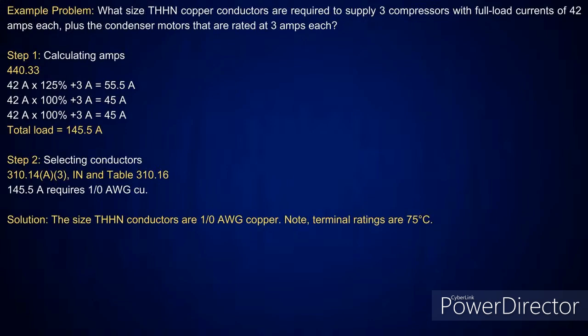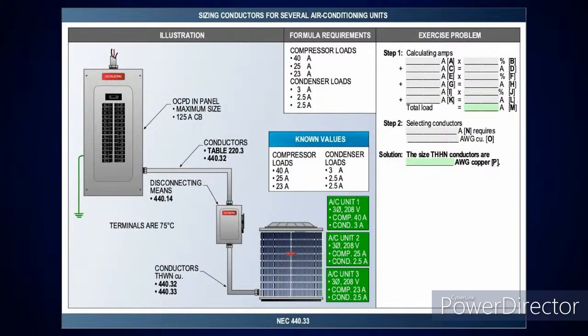Now, the thing I like to point out here, have I changed any of these calculations really? The format, the layout, everything is exactly the same. The only thing you've got to remember is how to do each one of them. You just have to be careful, because you don't want to assume you can just wire everything with a 1-aught. This was just to show how all this worked. We did it in a single line diagram because otherwise we couldn't get everything on here. We do show we've got three AC units. So basically, what would I do out there? I'd put in a wireway, and then I'd tap off of that for each individual one.